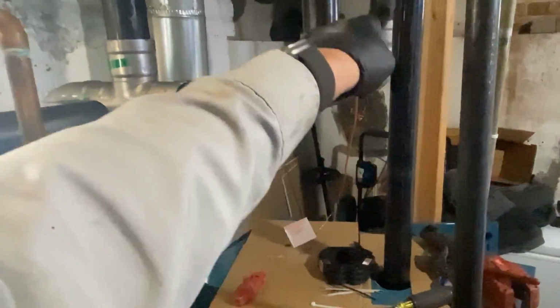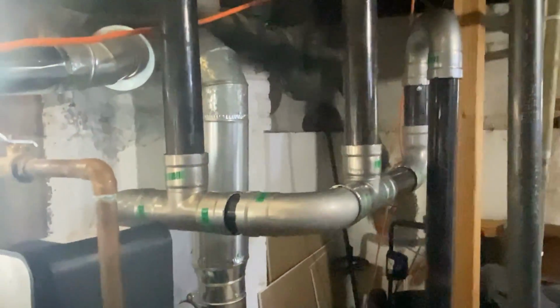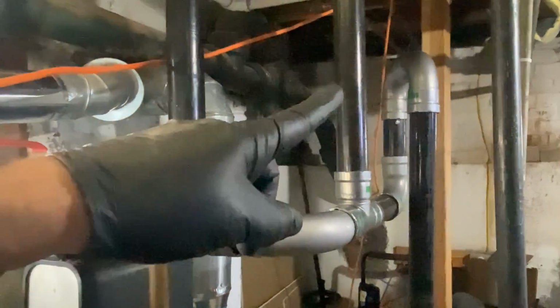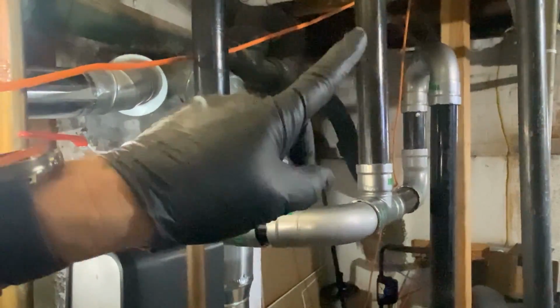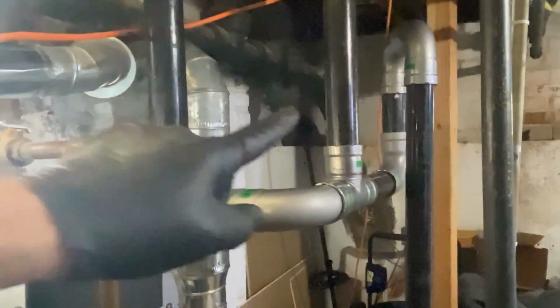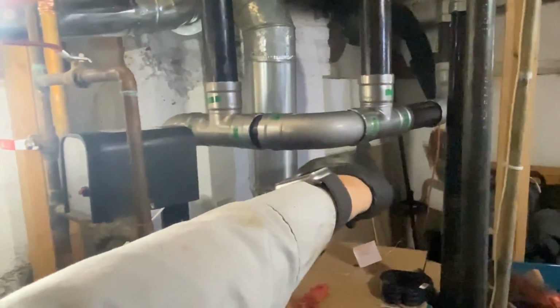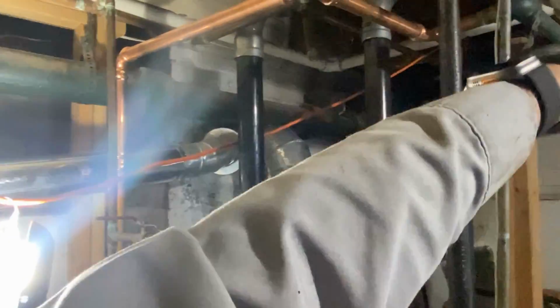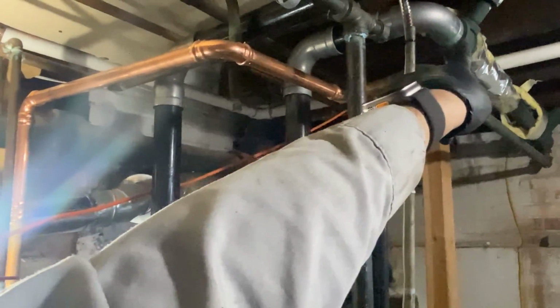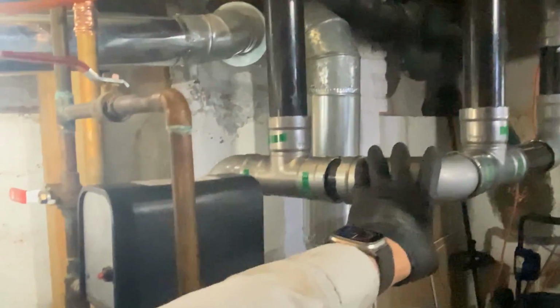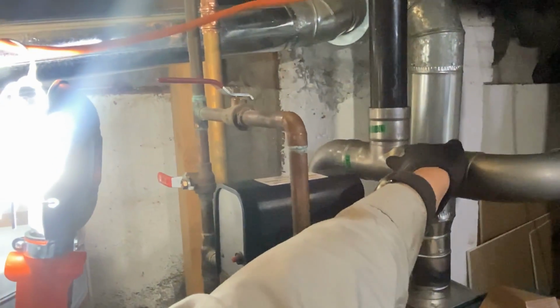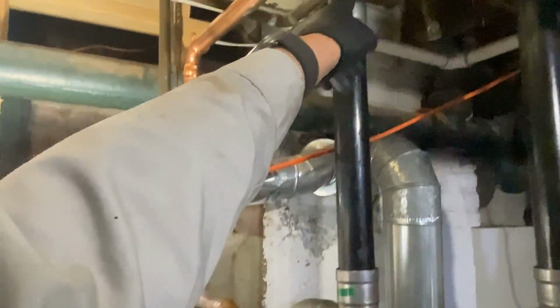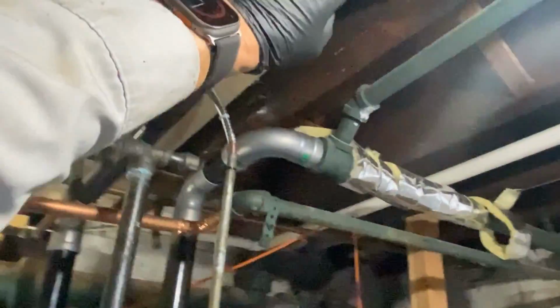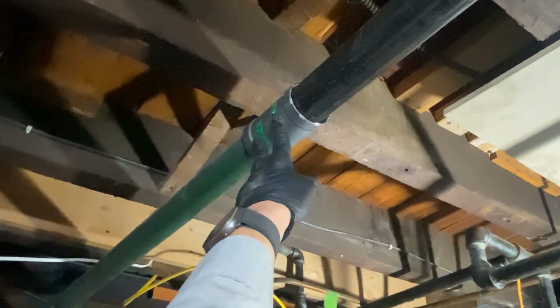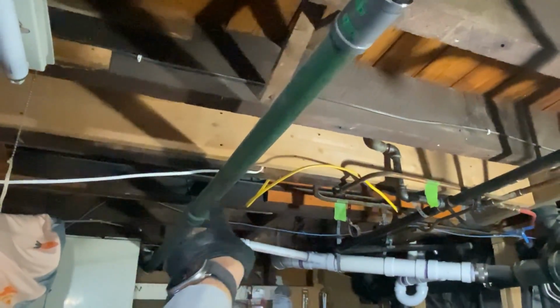Top of the boiler, we came up with, I think that was a 30 or 40 inch piece. It was high. Complemented that with 2-inch Viega MegaPress 90, street 90, another 90, a nipple, a T, with our nipple picking up our first steam main, with a 90 and 90. Little nipple coming out, that was just good enough. Street 90, our T, thermostat. Nipple, 90, another long nipple here, an elbow, and then our 2-inch MegaPress coupling to pick up the steam main that's going towards the front of the house.